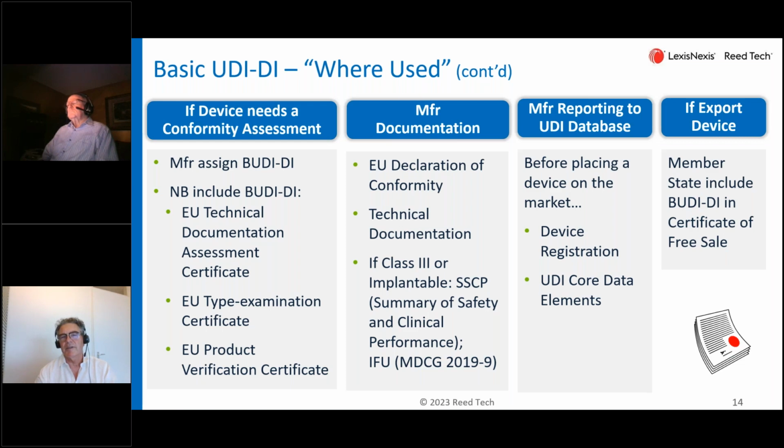And then, of course, you have other markets that accept CE marking, but then you need to have your certificate of free sale. Like the Middle Eastern markets, a lot of markets use that, where you can get access with a CE marked device. But you need to have this certificate of free sale, where it says that yes, this is a CE marked device. It is on the market in the EU. It's sold here, so it can also be sold there.